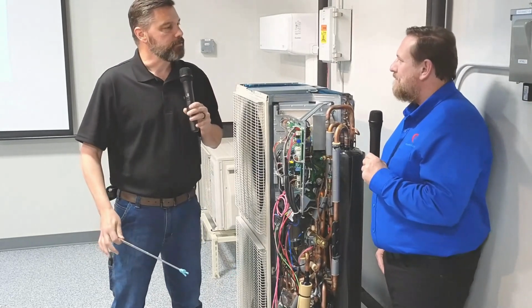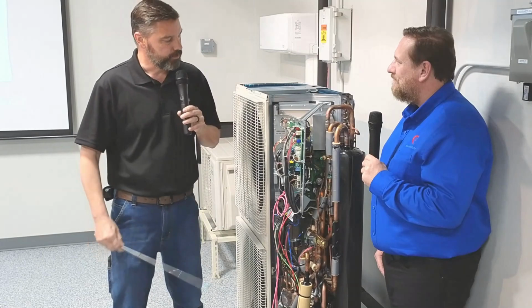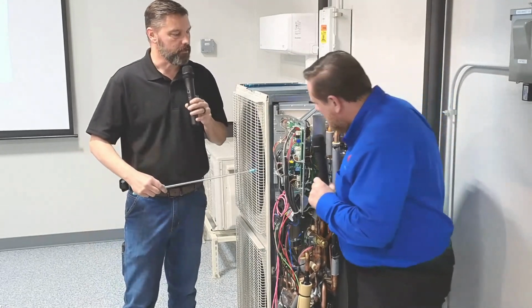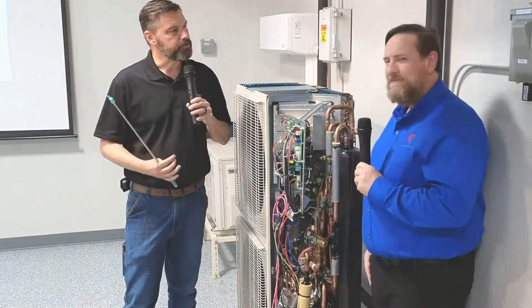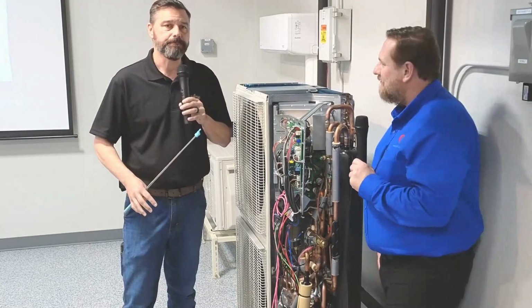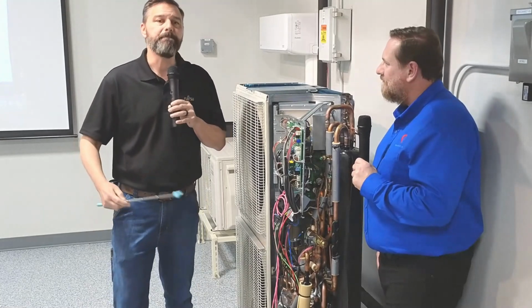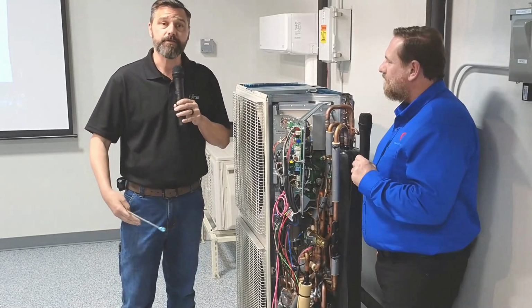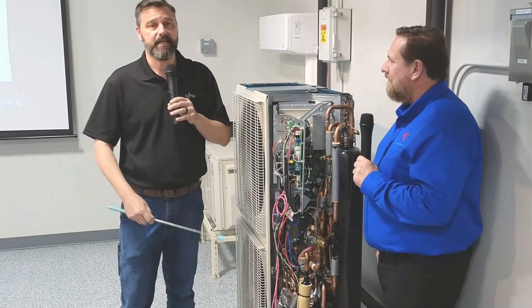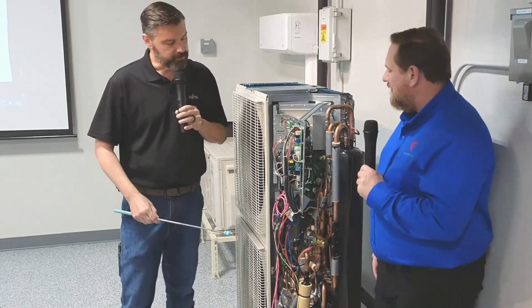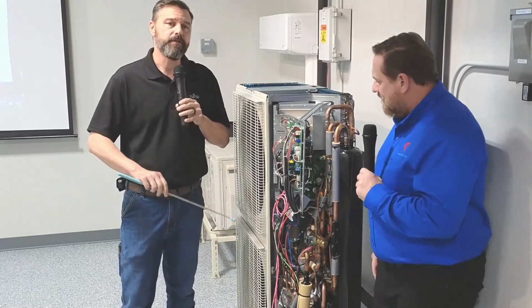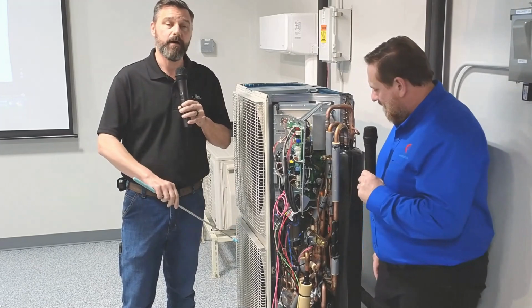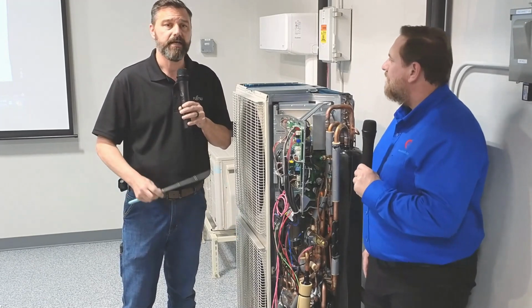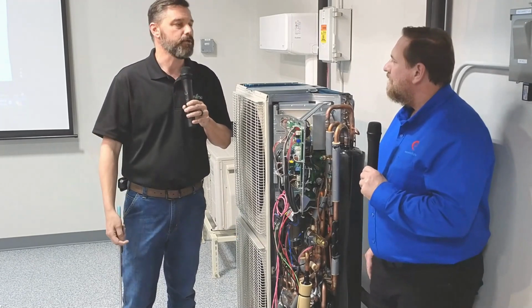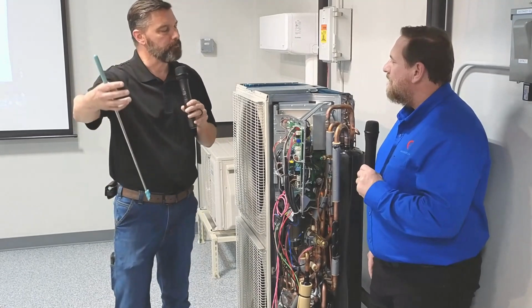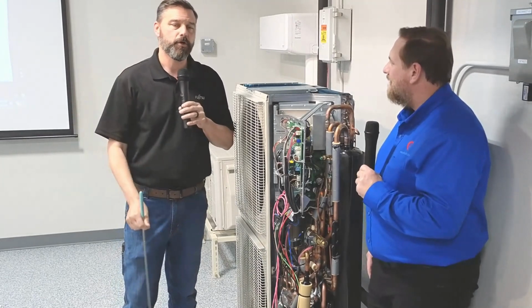So now let's take something new that they might not be as familiar with. We've got our printed circuit board here, where we're monitoring all of the temperatures and pressures through the entire system. And then the system is responding, managing that refrigerant flow based on changing conditions inside and outside. One of the other additional components is that we've relocated the expansion valve from the outdoor unit, like you'd see on a traditional mini split. The EV is located at the indoor unit now, and that helps get us longer pipe lengths for some of these larger commercial projects.